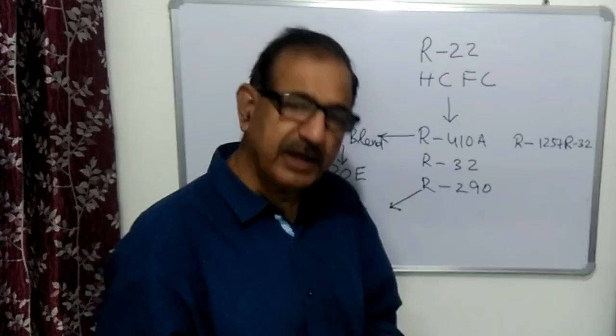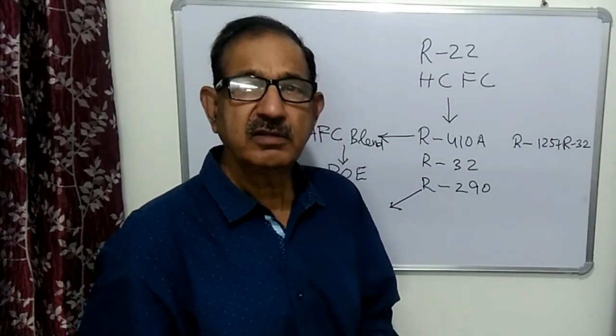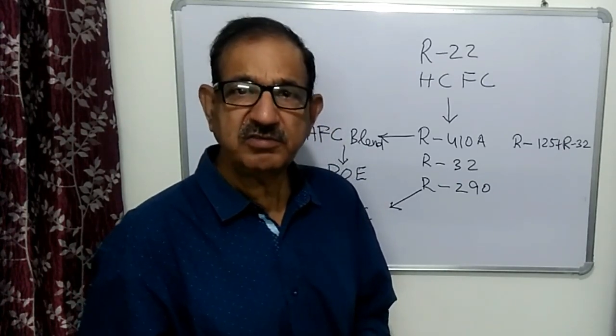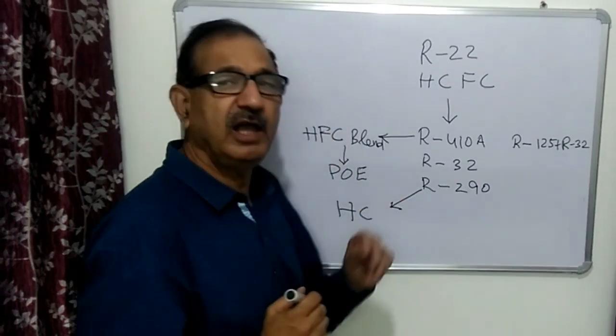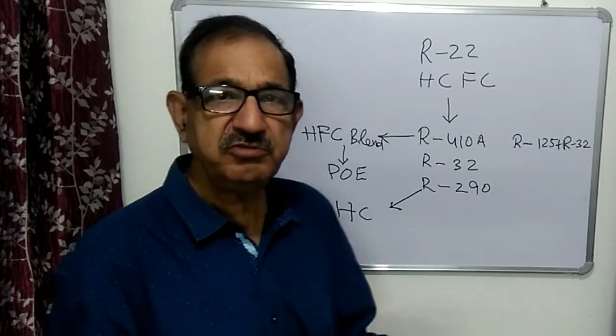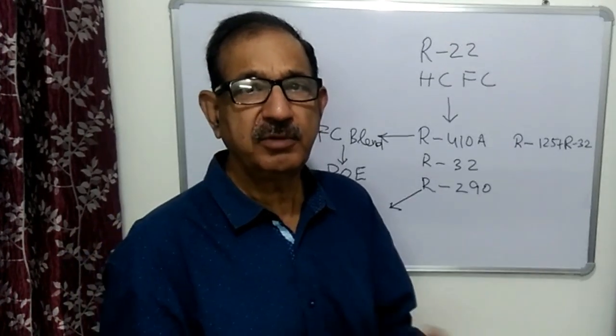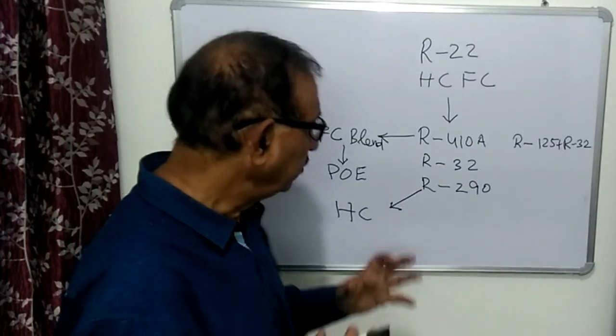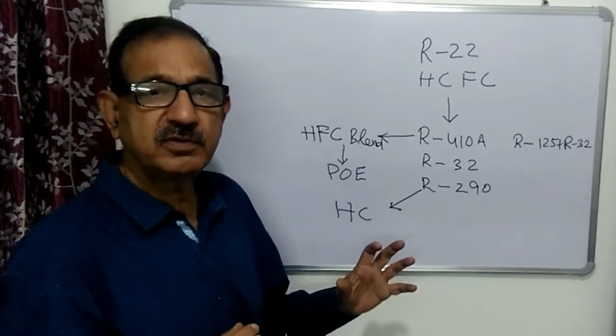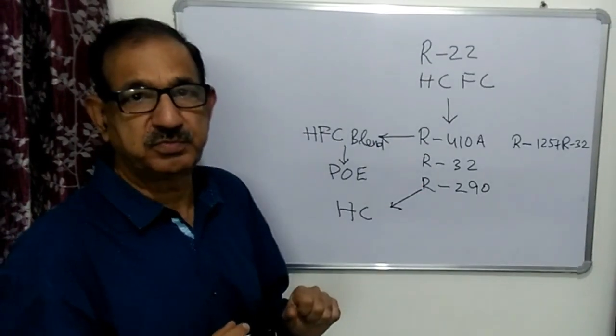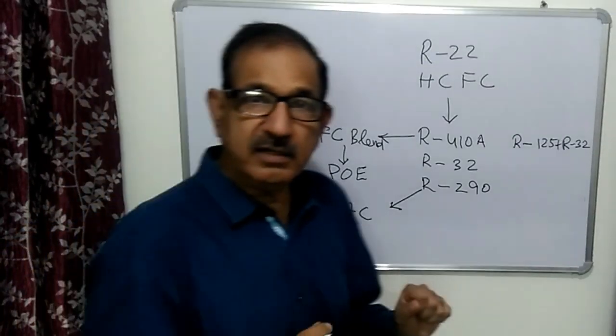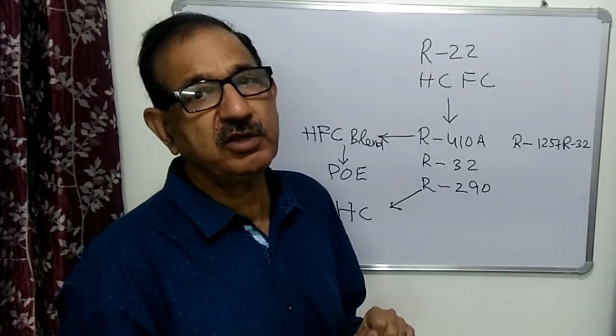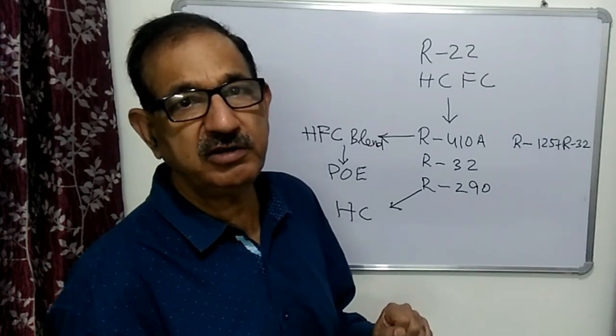The third refrigerant is R290. This is a hydrocarbon — HC — refrigerant. All hydrocarbon gases are flammable, and R290 is highly flammable. The flammability range is between 2% to 10%, so we have to take care of the flammability issue. There is also a restriction on how much of this refrigerant we can charge.